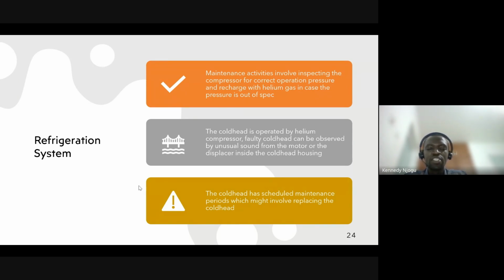To maintain the helium in liquid state, you need something called a cold head, which operates at this temperature and cools the helium gas back to liquid. The refrigeration system has the cold head, which is powered by a helium compressor - almost the same as the one used for refrigeration at home. The important things to check are the pressure of the compressor and the cooling of the compressor.